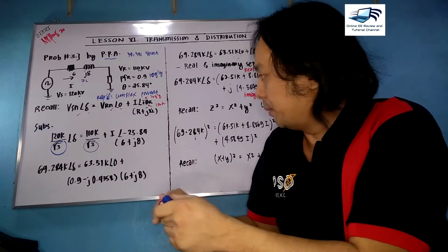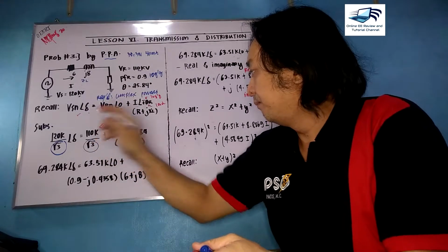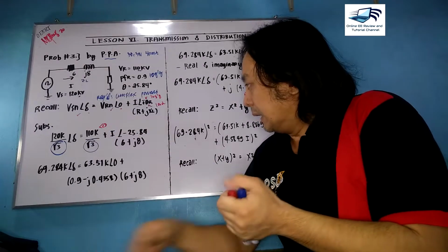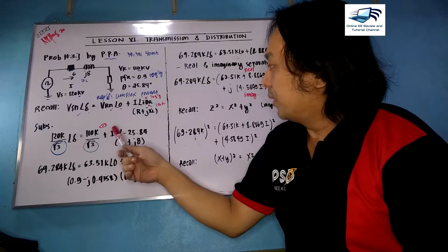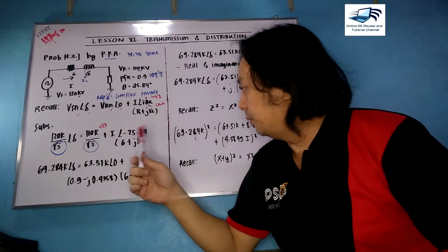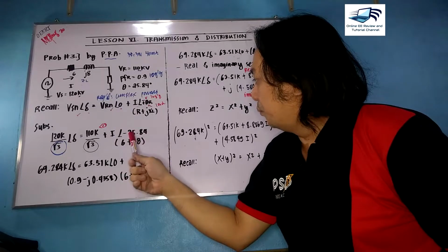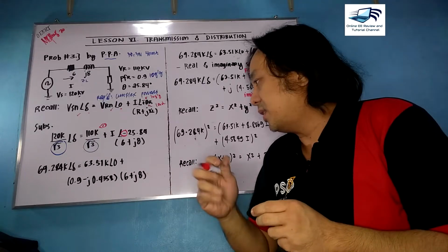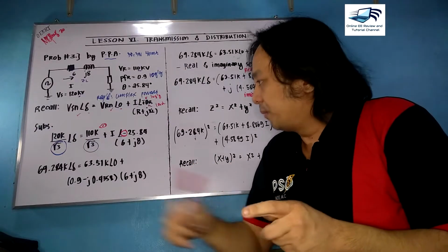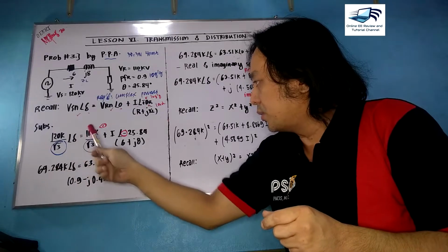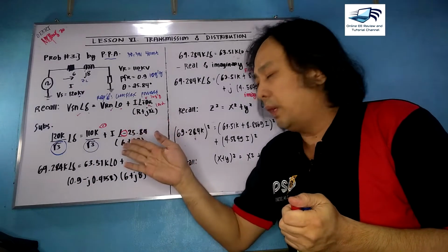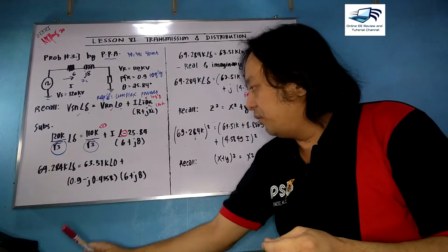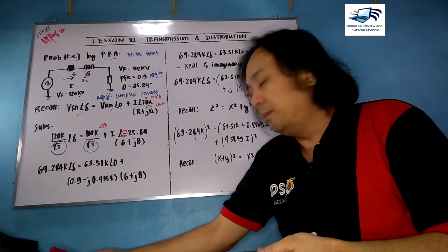I forgot to mention the bar zero here, but anyway, it will not affect the equation or the term. Now you have here your current as your lone variable, which is the unknown, and then 25.84, the negative here is a lagging condition, and then your ZL, R plus jXL. Okay, what I've done is simplify into numerical values the 120K over square root of 3 and 110K over square root of 3, which is 69.284 and 63.51K respectively.